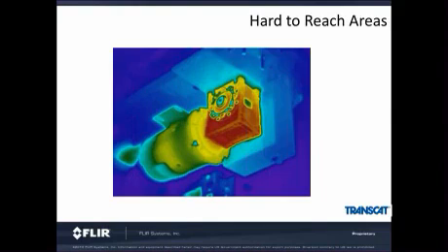On top of that, as we can see from this picture, the worm gear is elevated. We are looking underneath it, making direct contact very hard and not likely. Our industrial facilities and plants are chock full of applications like this, where in the past we would run them to failure because discovery would be difficult at best. But with the thermal imaging camera, being able to measure temperature and seeing the difference in temperature indicating a problem, that may no longer be the case.